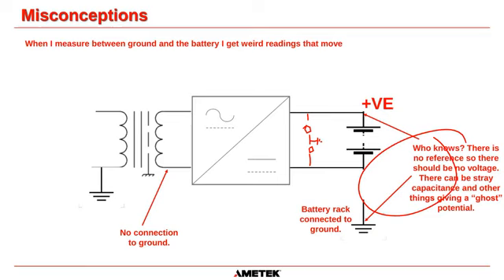If you're getting weird readings and you have ground fault detection, then you have to do further investigating. Okay. But if you don't have ground fault detection in your system and you go between positive and ground and negative and ground and you get weird readings, then that is normal. Absolutely normal.